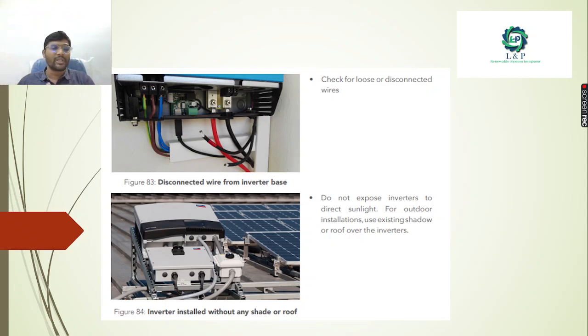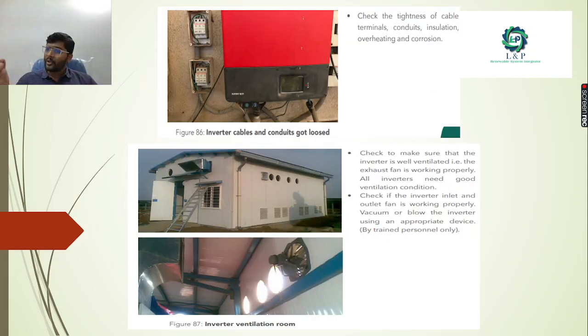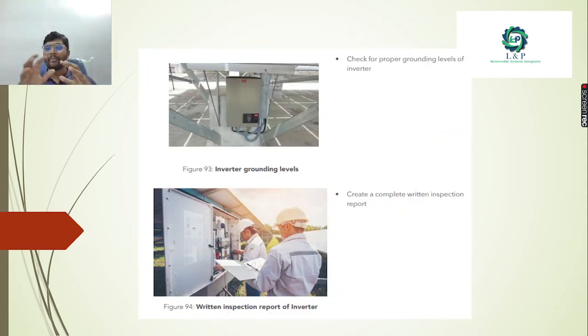Do not expose your inverters to direct sunlight. Always install your inverters under a roof, and if you can provide the room with ventilation also, it is a good one. And make sure the cables and conduits are properly tightened. If they are loosened, there is a possibility for power reduction. Check that proper grounding of the inverters is there, and keep a complete written report of the things that you observed during your testing, along with the date and time.